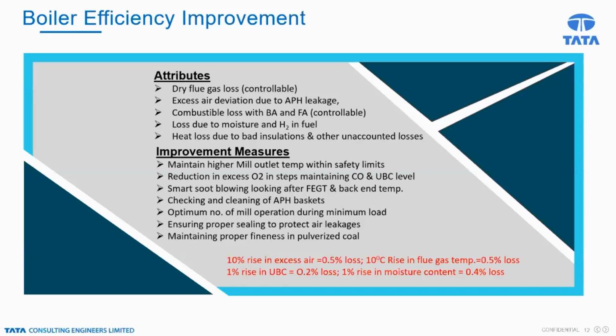So how will we be able to achieve that? Maintain a higher mill outlet temperature, reduce excess O2, and do smart soot blowing. Actually, soot blowing is very important. Otherwise, the surfaces will not have proper heat transfer, which will affect the complete heat pickup by the various pressure parts, and it will affect the back-end temperature, so the dry flue gas loss will be directly impacted. Also, check and clean the air preheater baskets, and keep an optimum number of mills in operation during minimum load. This is also very important.